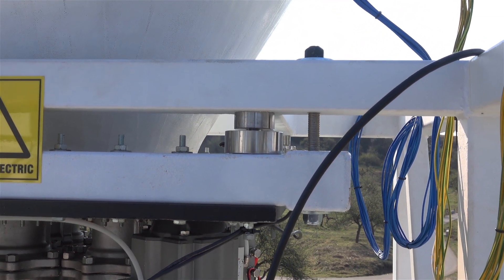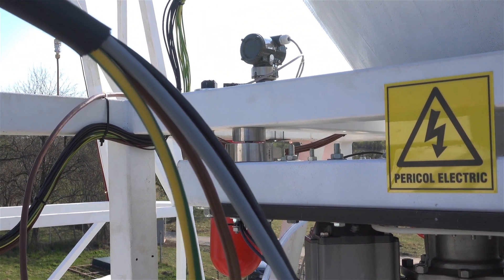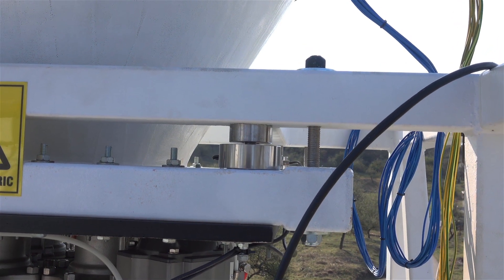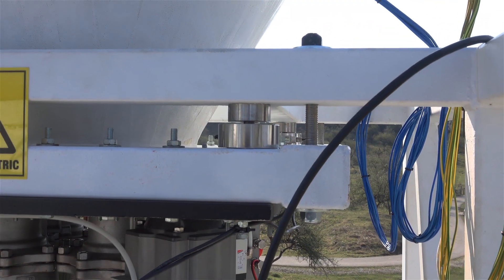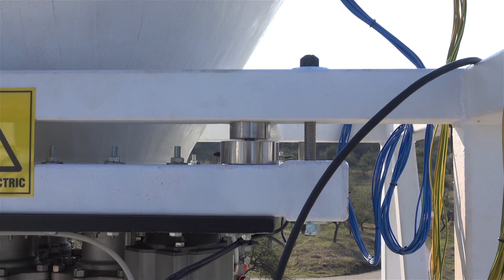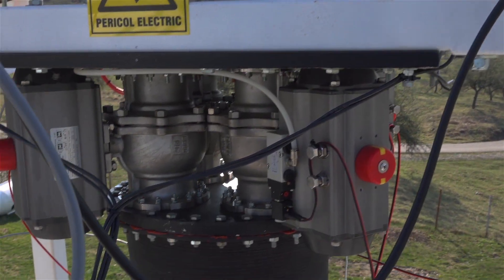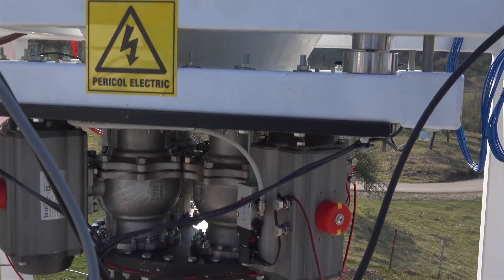I'm going to start with the load cells that are measuring the engine's thrust. Basically, the whole test article is mounted on a metallic structure, and between the test stand and this square metallic frame we have the four load cells. These cells are able to measure thrust between 0 and 40 metric tons, but this engine is rated to only 25 tons, so we are more than covered.